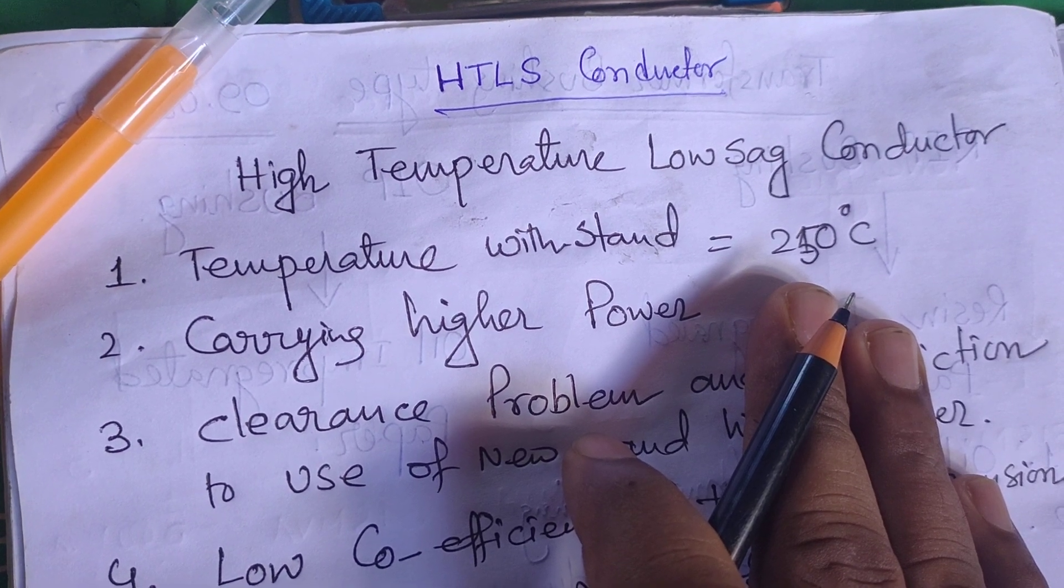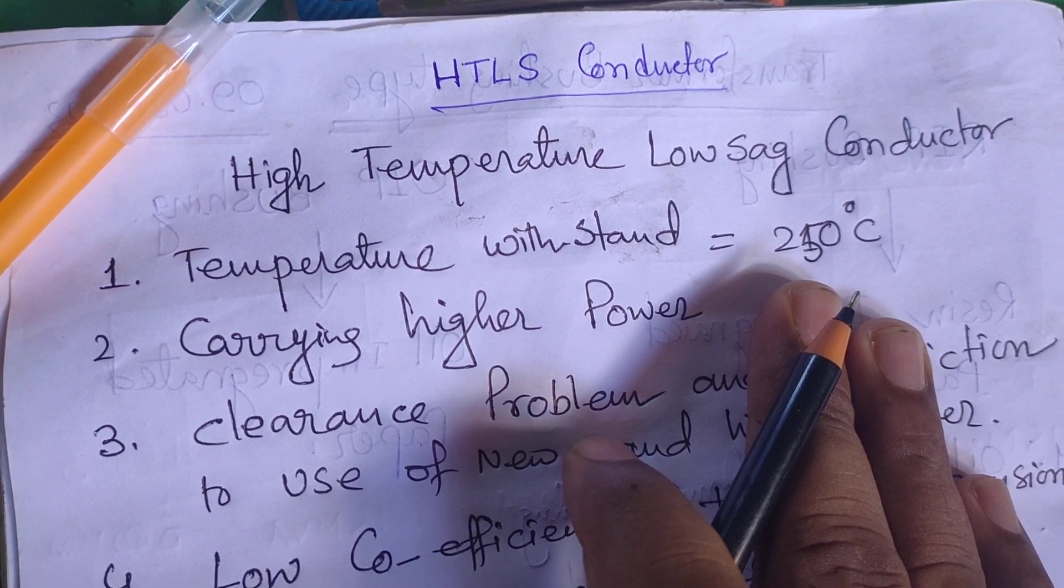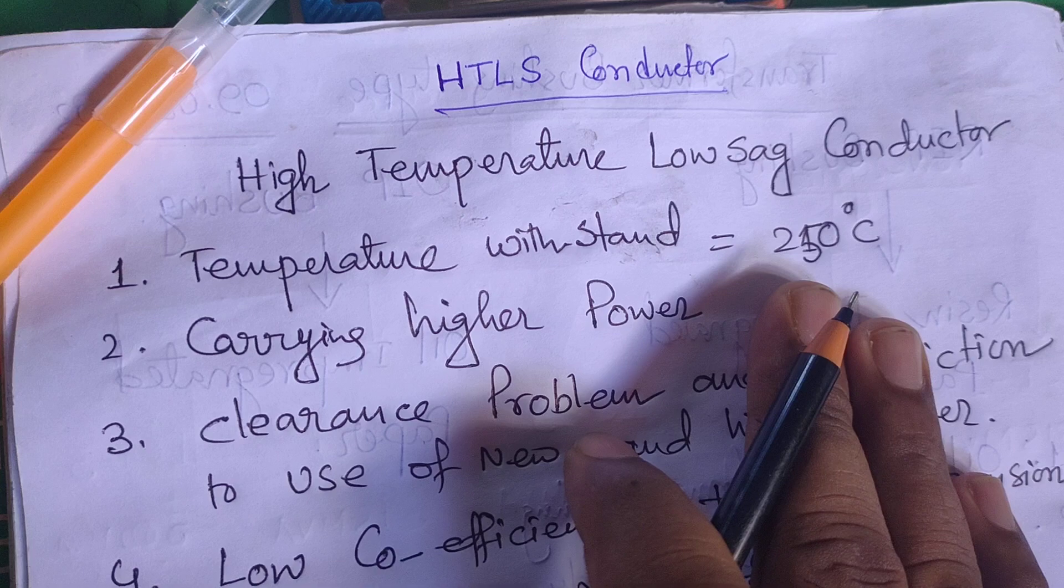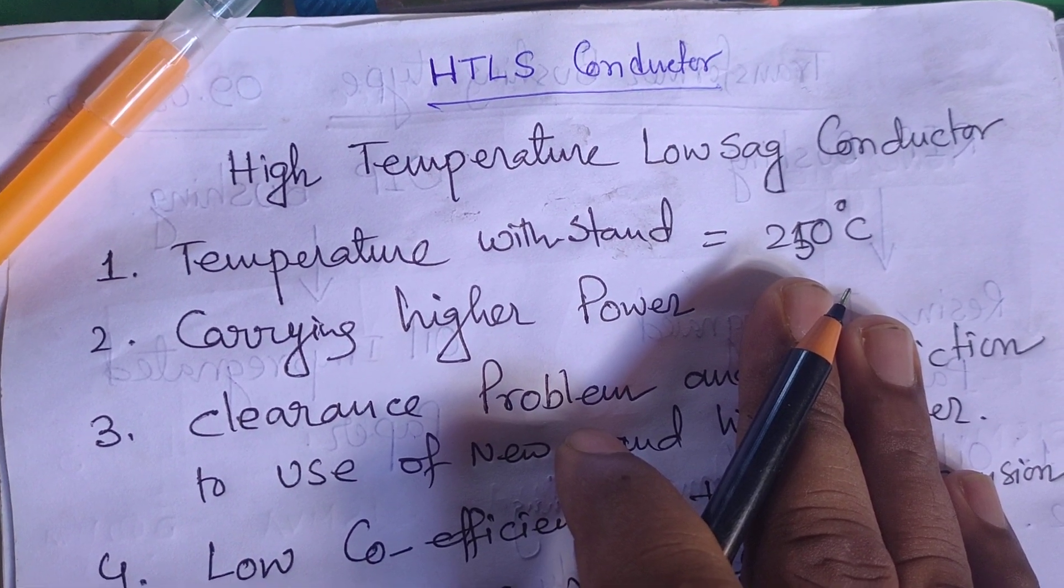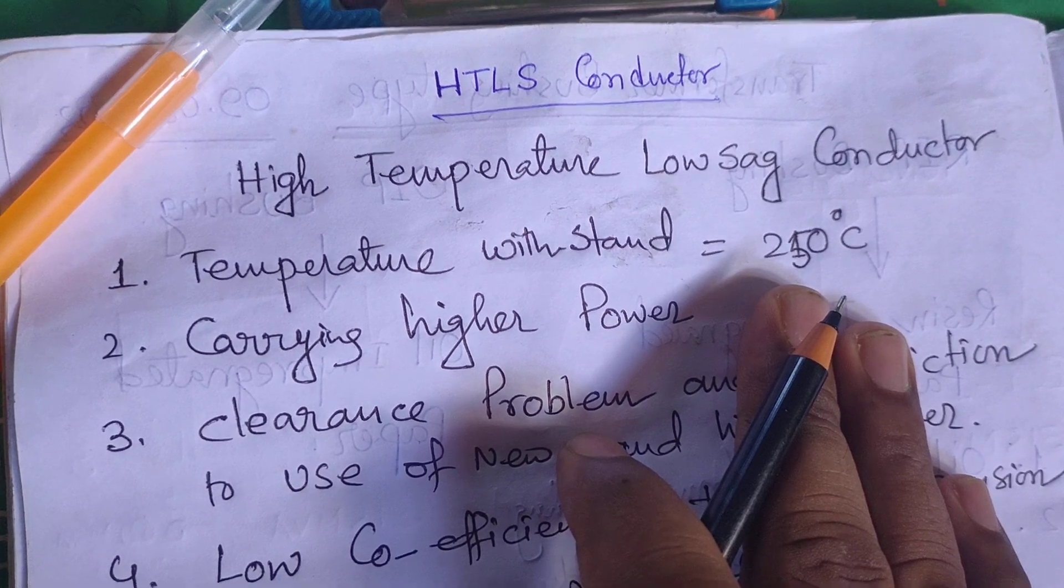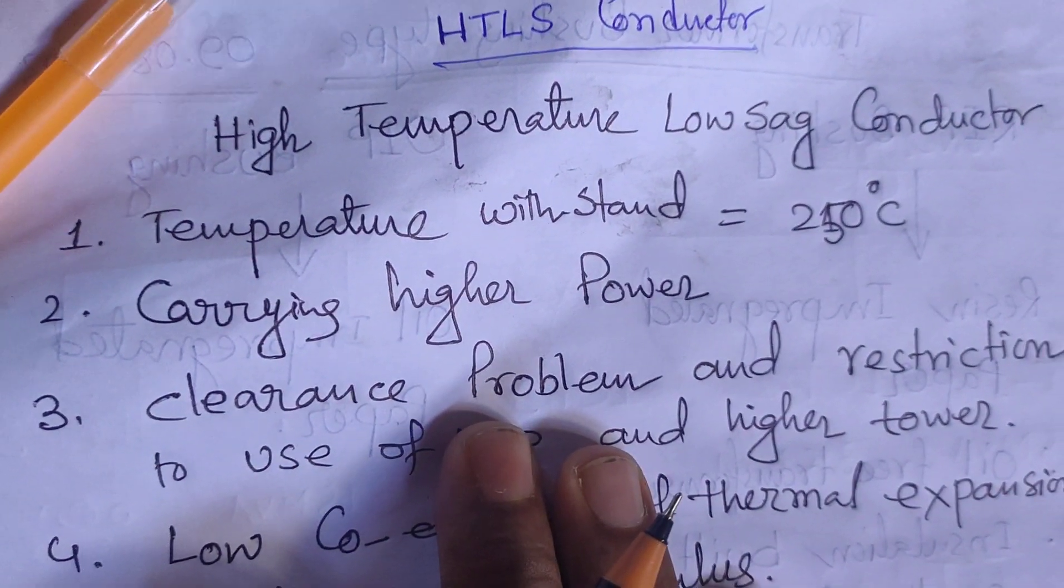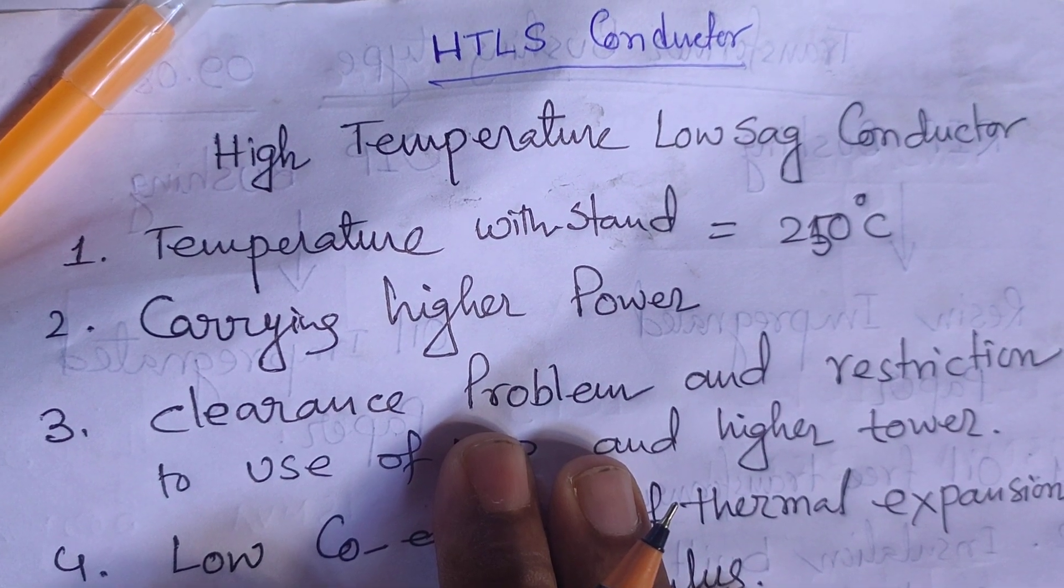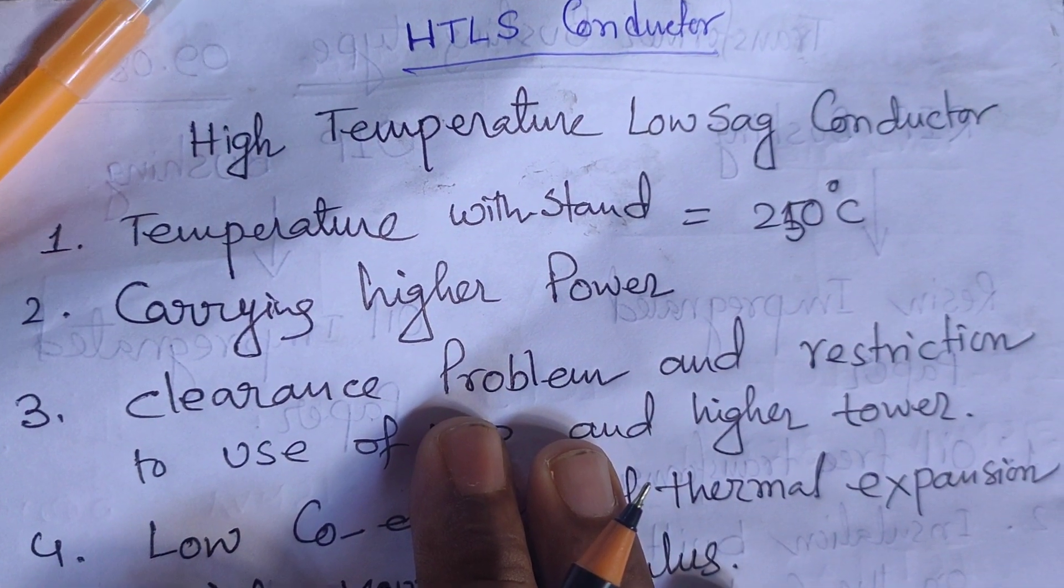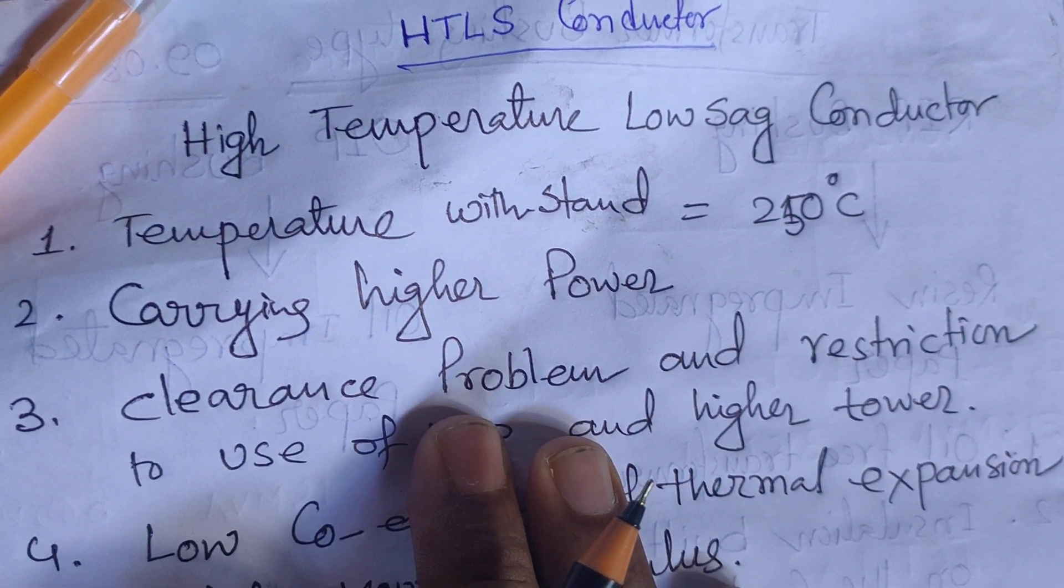The factors related to tower position, sag clearance, and old tower conditions are considered for installing HTLS conductors. The temperature withstand capacity of this conductor is 250 degrees Celsius. It has the capacity of carrying higher power, meaning higher amounts of current can pass while sustaining high temperatures without affecting performance or requiring further economic investment.